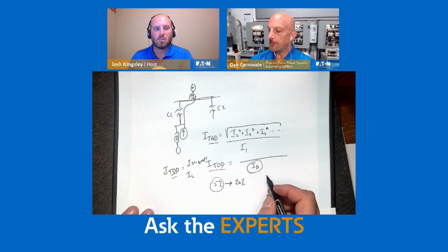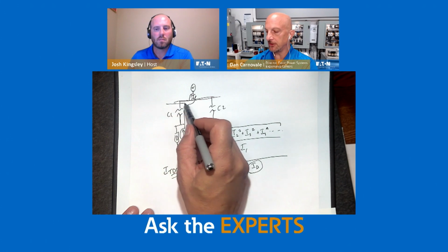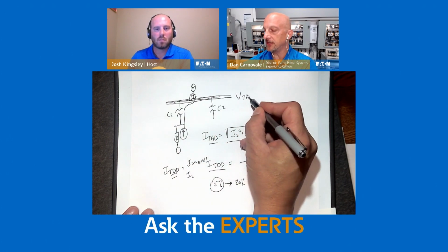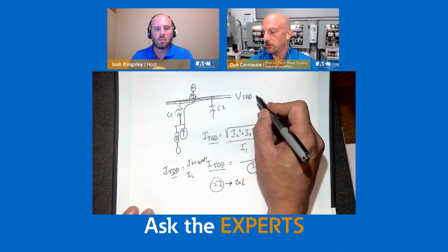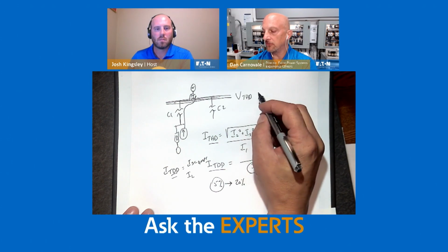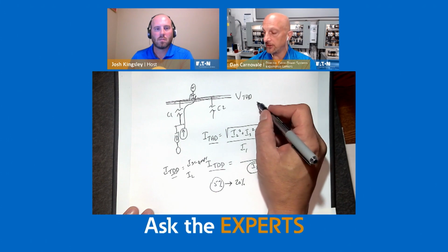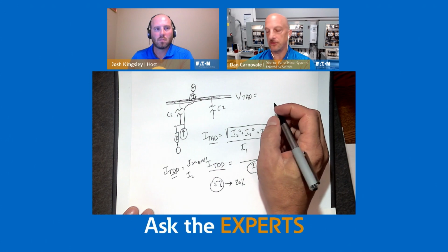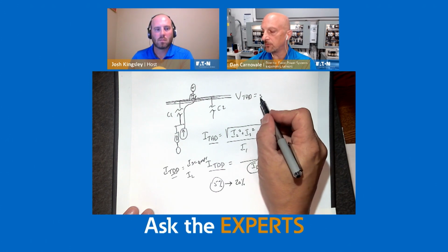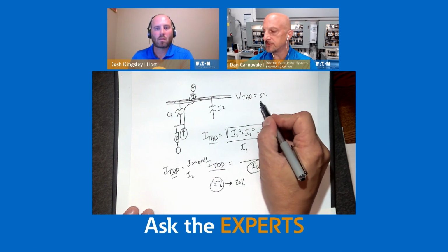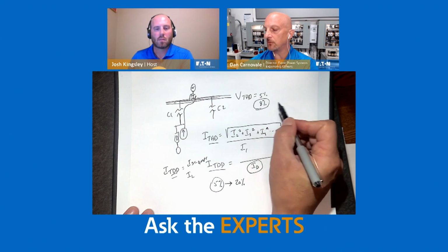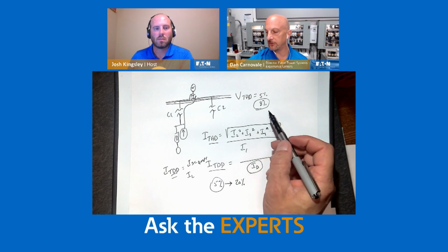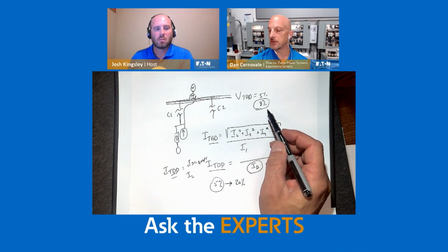But the voltage distortion levels, the part that it's really referring to more importantly, is VTHD here, usually, and that goes by voltage level. So if I'm at 480, for example, that's the one change that was made from 1992 to 2014. It went from 5% THD to 8% THD. And what they found was you didn't have to be quite as clean on most power systems at 480. So you could allow a little bit more voltage distortion.